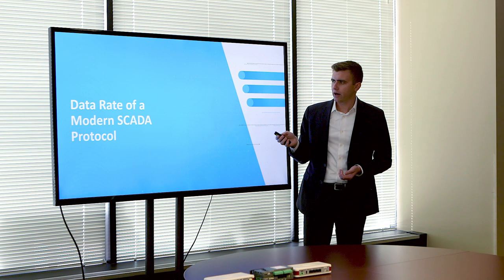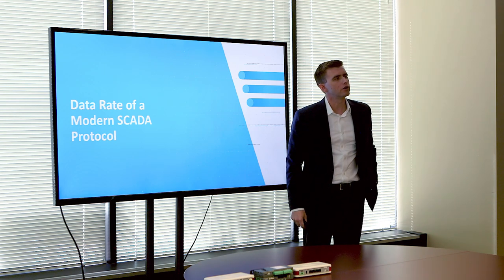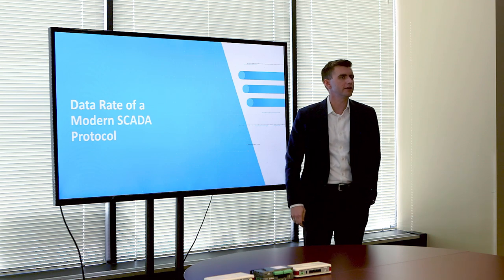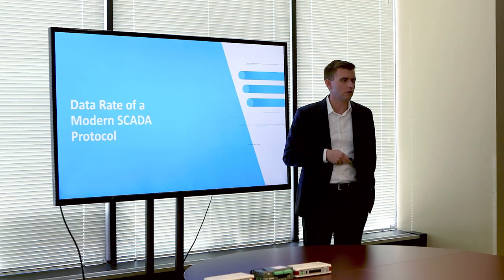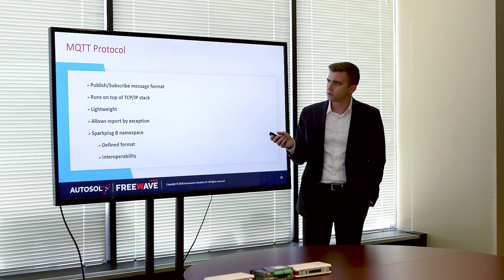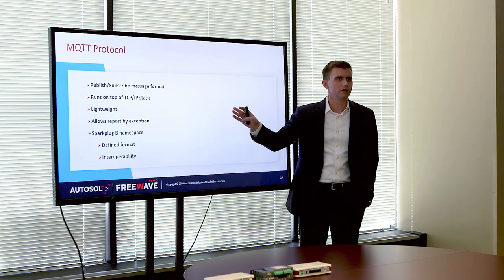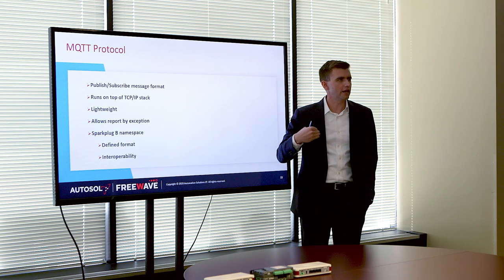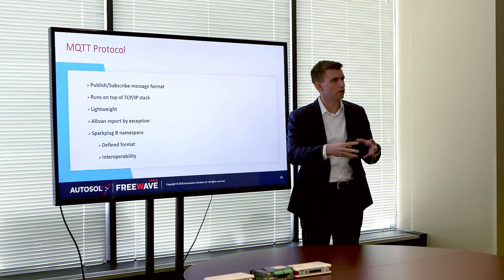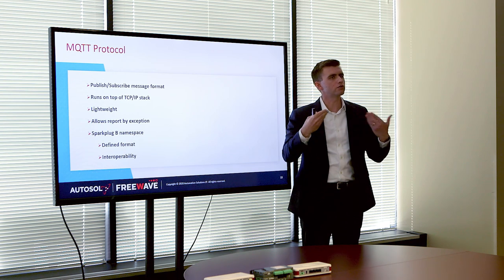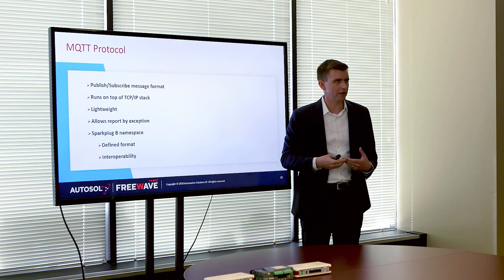Now I'm going to talk about how this stacks up compared to a modern SCADA protocol called MQTT — specifically MQTT SparkplugB, which is what we used for these tests. MQTT is a publish-subscribe message format. The edge devices like Edge ACM publish data up to a central broker, and then other software subscribes to that broker for specific pieces of information.